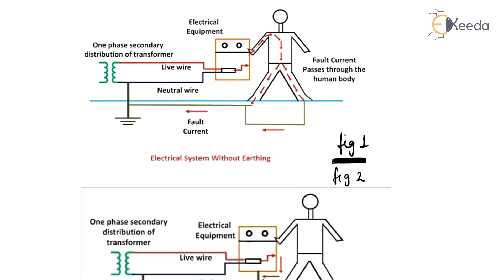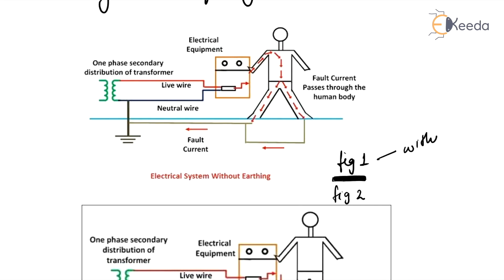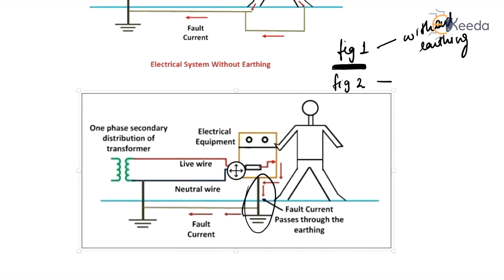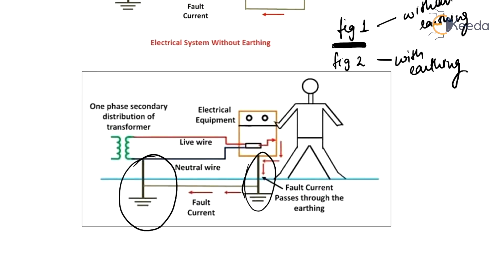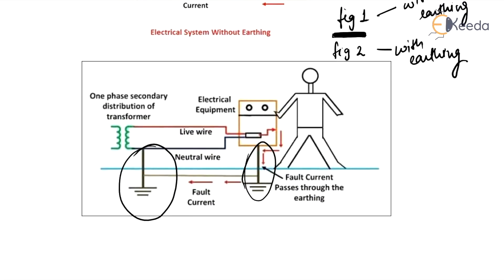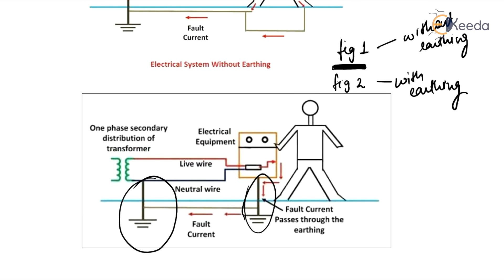Here are two figures. Figure one shows the electrical system without earthing, and figure two shows the electrical system with earthing. In the second figure, earthing is done by electrically connecting the respective part of the installation to a system of electrical conductors or electrodes placed near or below the ground level. The earthing mat or electrode under the ground has a flat iron riser through which all the non-current carrying metallic parts of the equipment are connected. When a fault occurs, the fault current flows through the earthing system to the earth, thereby protecting the equipment.